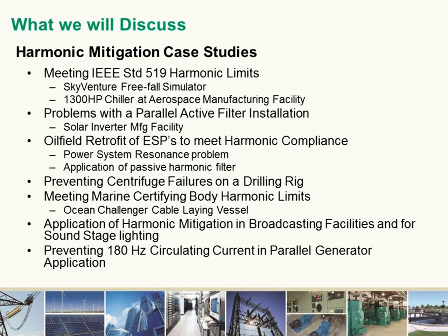We'll look at how the harmonic limits defined by IEEE Standard 519 were met in two different applications. We'll highlight an example where harmonic treatment through active means led to serious side effects due to the very high frequency harmonics it introduced. We'll see how harmonic resonance created extremely high levels of voltage distortion in an oil field, and what was done to address this condition, and how passive harmonic filters were applied to comply with the IEEE 519 standard.